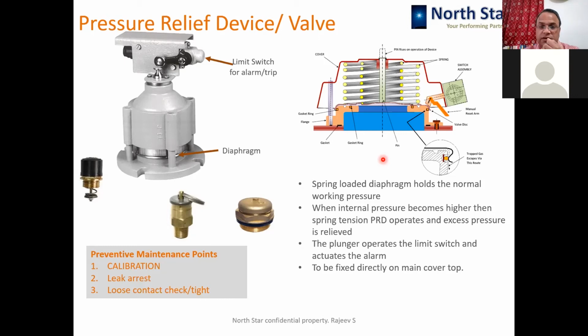For large transformers, the PRD is also subjected to calibration, where it is taken back from the transformer and calibrated either at the manufacturer's end or at laboratories, so that you are sure that they are operating at their defined pressure. Okay, leak arresting, of course, it is a pressure relief device. It has to be leak proof, so any oil coming out of it is to be arrested. And you have a micro switch or limit switch on this device, so you can maintain it the way you maintain any electrical circuits.